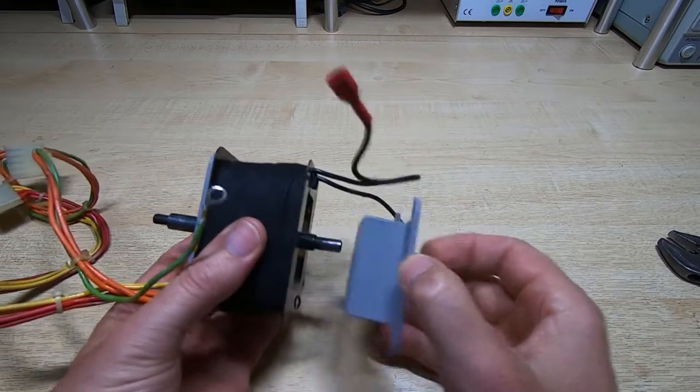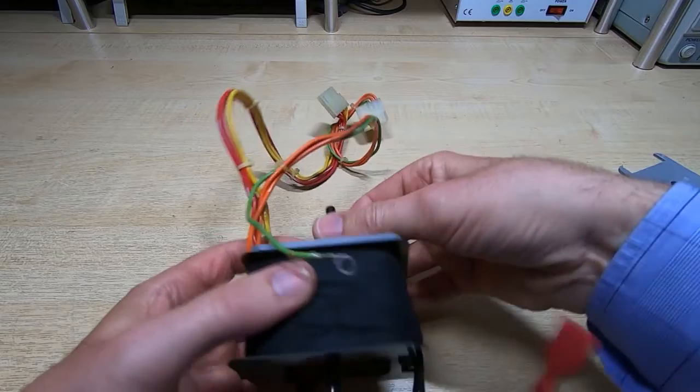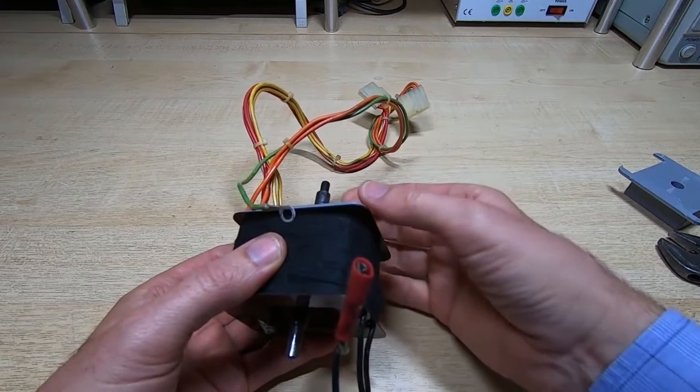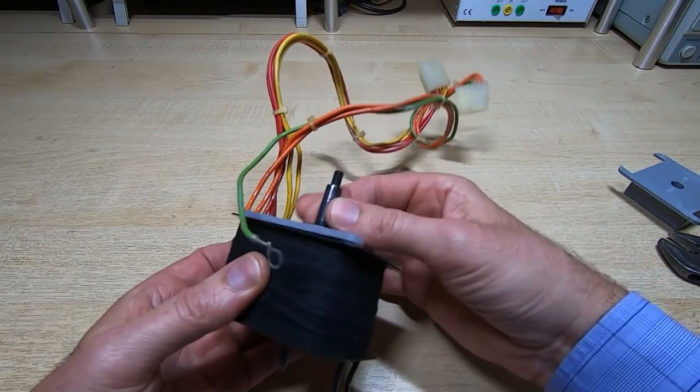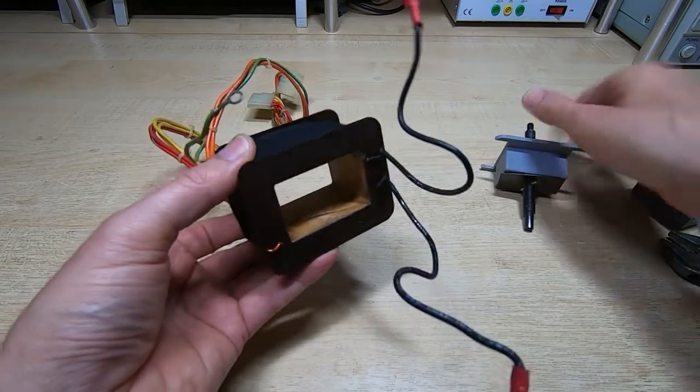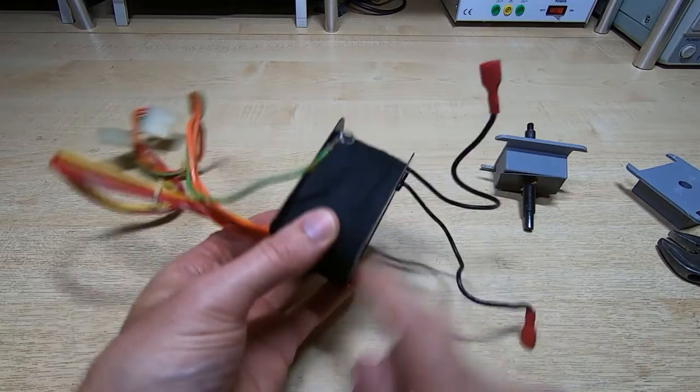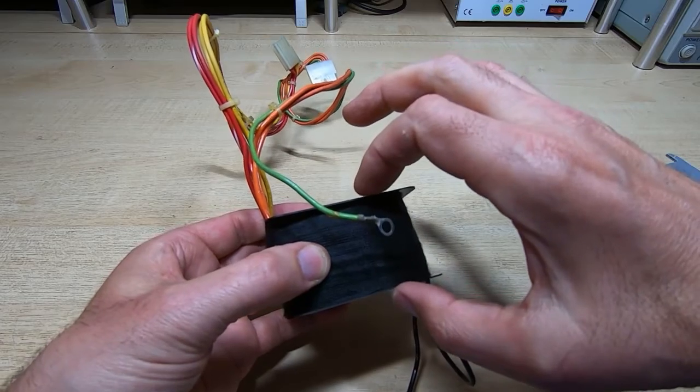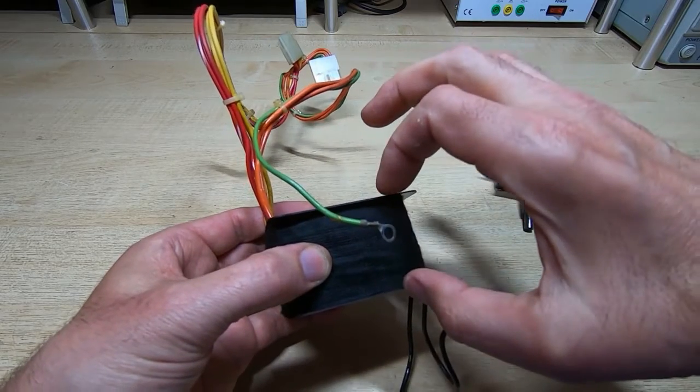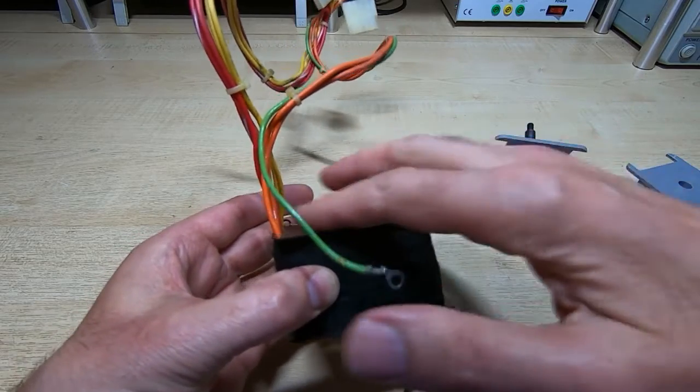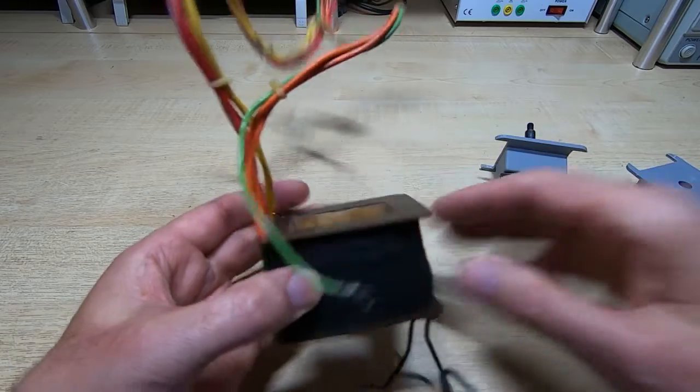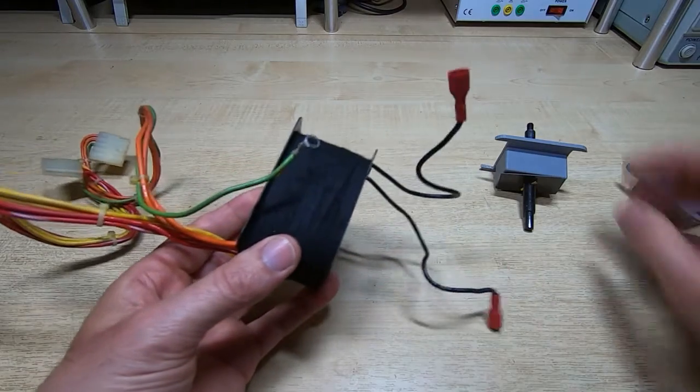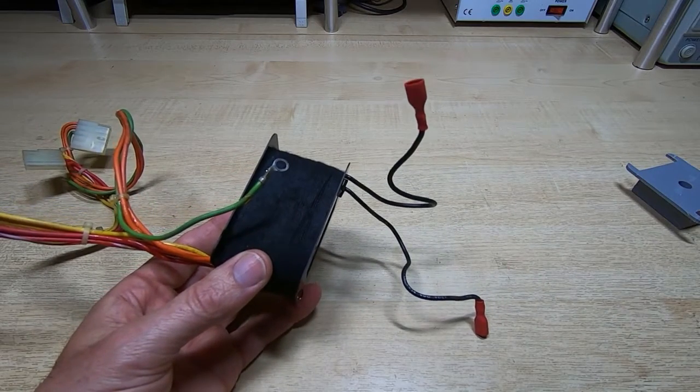What we're looking for is these will be loose. If they've gone very tight then we may have a problem getting the laminations in, but as you can see these are about the same as when I fitted them. No real distortion, the side cheeks are not bowed out. We've got a nice straight profile to the sides and so the next thing is to refit the laminations.